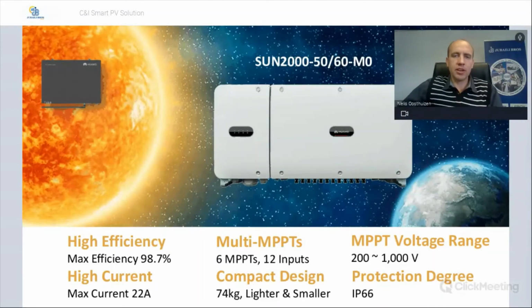Then the next range of C&I inverters is the 50 or 60 M0, so it's still the first generation of inverters of this size. 98.7% efficiency. Please note again, the maximum current is only 22 amps on this first generation inverters. This specific range of inverters has got 6 MPPTs, and then the voltage range for the MPPT is between 200 and 1000 volts.